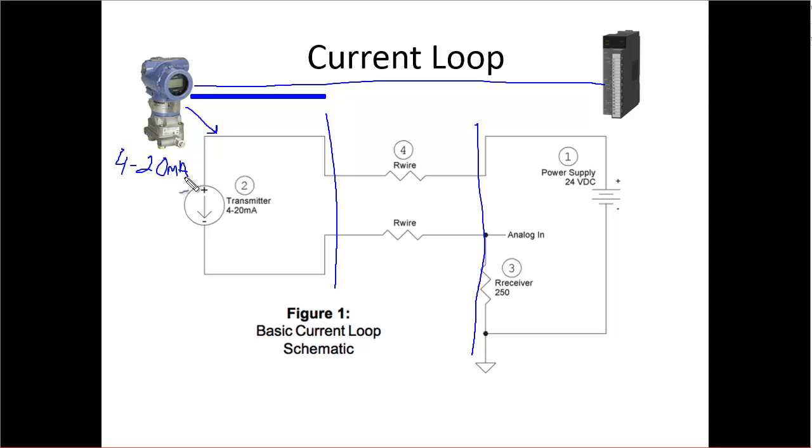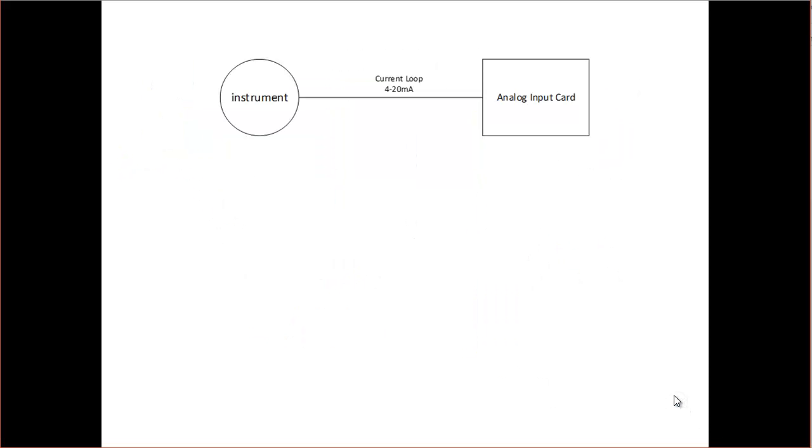It's going to be a 4 to 20 milliamp output signal that's going to travel through the wire here and go into the analog input card which is going to convert that current into a little voltage that's going to go down to our A to D converter. So an end to end example, let's just talk about the math that's going on behind here.